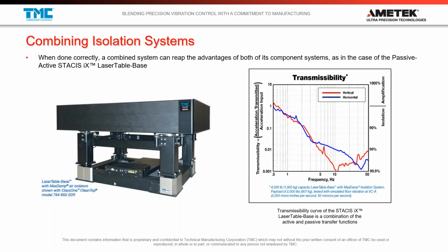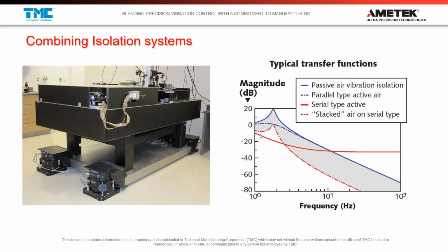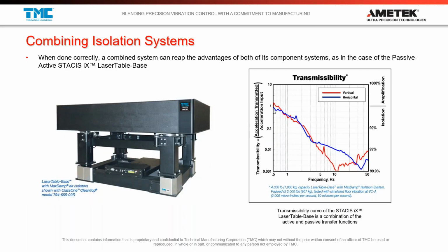And when we tune the active isolators to really hone in on that resonance, and then we add some damping fluid and start to dampen out that resonance, you can provide a system that actually doesn't necessarily show this performance loss. When built correctly and packaged together, you're still isolating at low frequencies quite a bit.